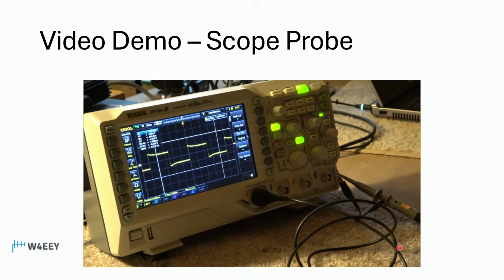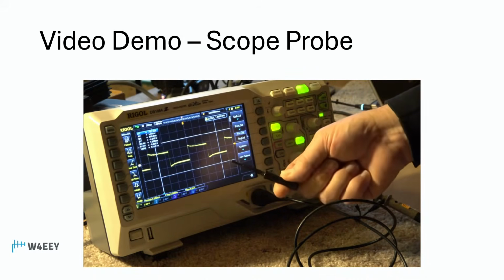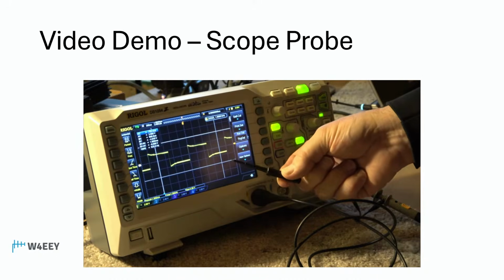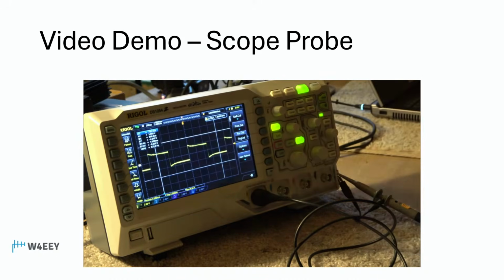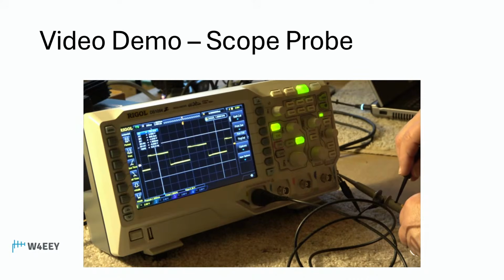The probe is in the times 10 position. You can only make this adjustment when it's in the times 10 position. And you have a little tool that scope manufacturers send you, or you can use a little alignment tool. It's just a small piece of metal held in a plastic holder so you don't get too much stray capacitance down near the control. And by adjusting the variable capacitor that's on the scope probe, see there, it's squared up. If I go too far, you'll see the leading edge becomes rounded. That's no good either. So you want to adjust it until your square wave is square.